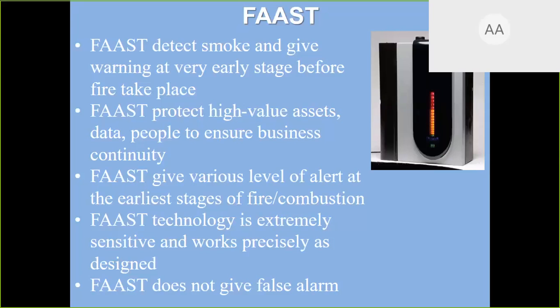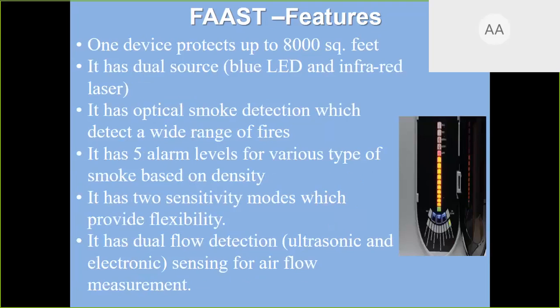FAAST technology is extremely sensitive and works precisely as designed. It has to be designed as per the customer's requirement, based on the area, height, hazardous material stored, and what type of fire is possible from that hazardous material. So it is designed, and it does not give false alarms. Once you install FAAST equipment in the production area, if anything happens, it will give you the alarm before the fire takes place. What are its features? One device protects up to 8,000 square feet.